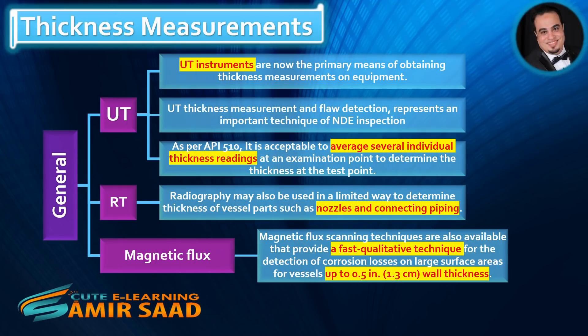General: UT instruments are now the primary means of obtaining thickness measurements on equipment. UT thickness measurement and flaw detection represents an important technique of NDE inspection. As per API 510, it is acceptable to average several individual thickness readings at an examination point to determine the thickness at that test point. Radiography may also be used in a limited way to determine the thickness of vessel parts, such as nozzles and connecting piping.